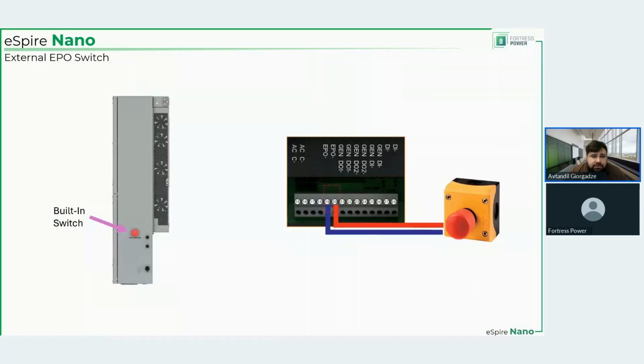Next, external EPO switch. As I said before, we have the built-in EPO switch that actually triggers the RSD. If you install an external EPO switch, that EPO switch will not exclude the built-in switch from the picture. It's going to be either or, whichever one is pushed. That is the one that is going to trigger rapid shutdown and emergency power off sequence, right?